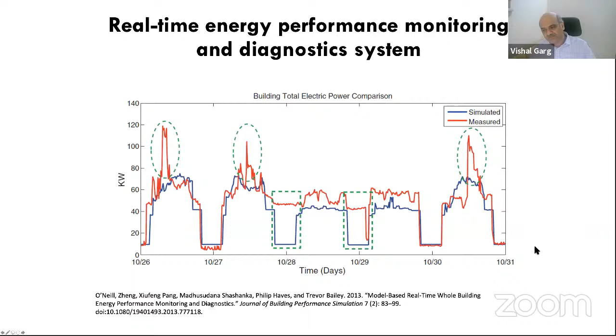For example, the blue one is the simulated load. According to this simulation, this should have been the load, but we are seeing a peak here, which means something is wrong. Then here we see that the blue load goes down and the red one also goes down, but here we see the blue going down while the red is not going down, which means there is a fault here, something wrong that needs to be checked. So we can have energy simulation running in parallel to the real building operation and do real-time comparison to detect such faults and try to fix them.